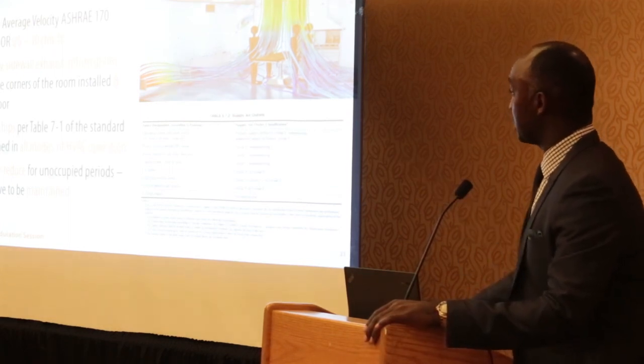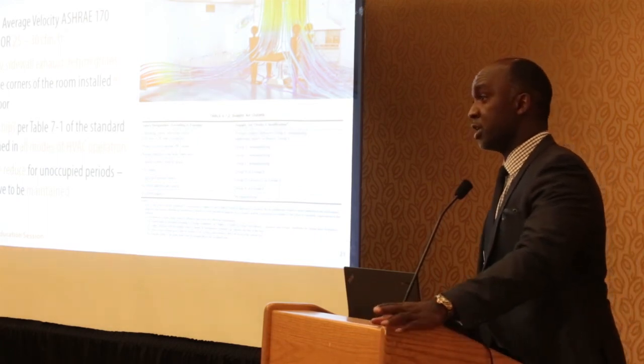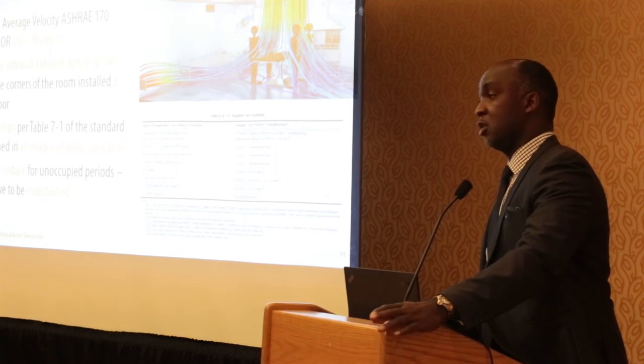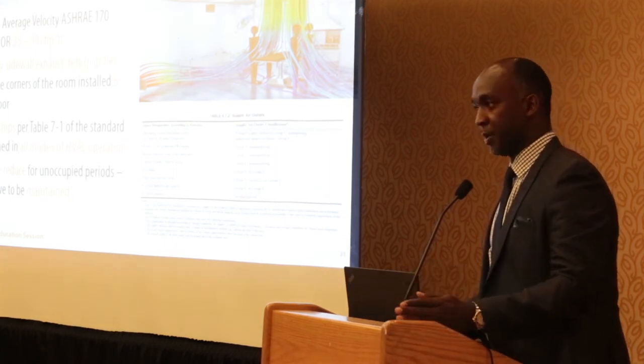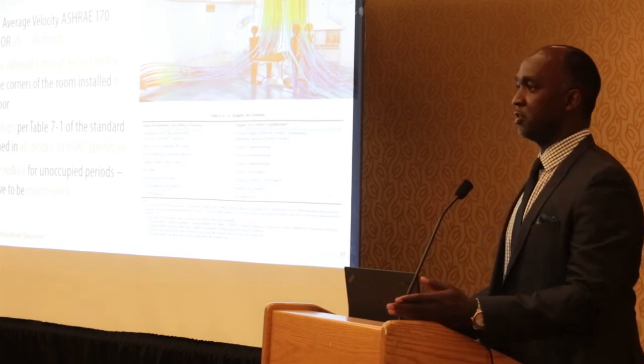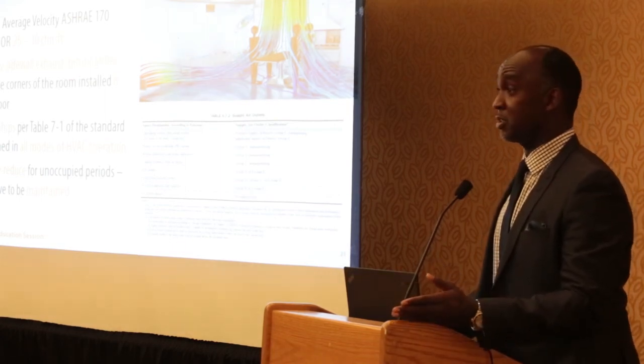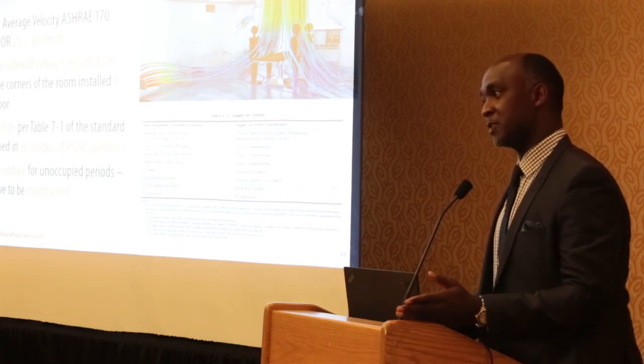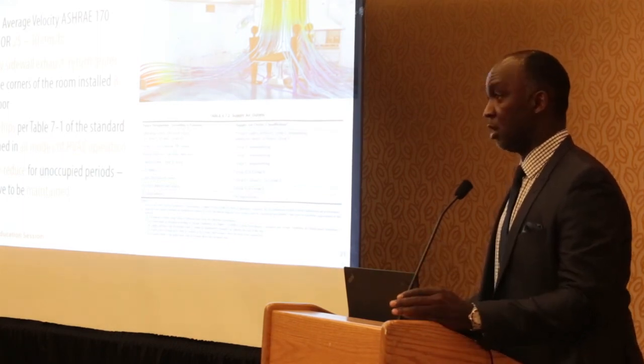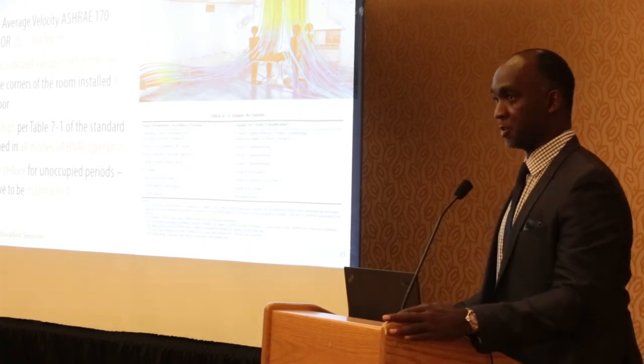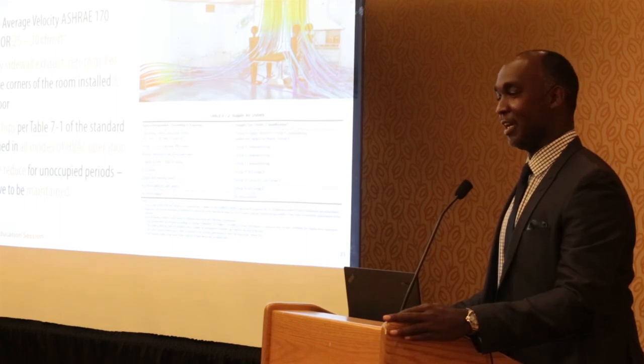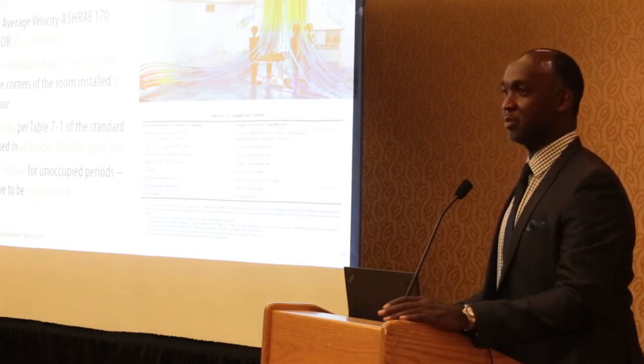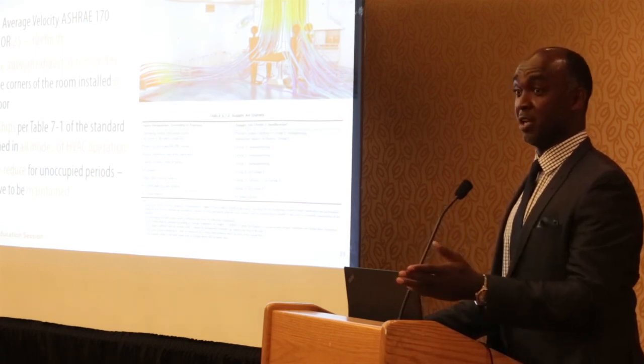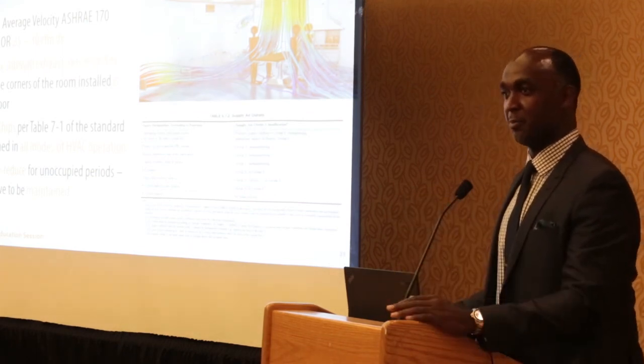As I said, the pressure relationship is extremely important, and I'm going to talk about different ways that you can maintain pressure within the space. And the code also says that you can reduce the air change. So if you have 20 or 30 air changes in your space, you're able to reduce it when it's unoccupied. If you have 30 air changes and you're able to reduce it to 10 air changes during unoccupied periods, you're saving a tremendous amount of energy. On a single OR, you can save up to $10,000 per year by using what's called the setback. You're basically setting back your OR so you can save energy if it's not being used.